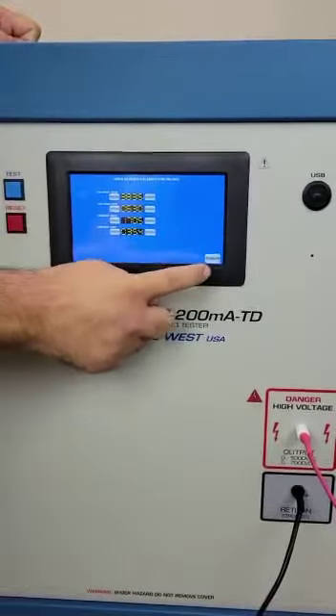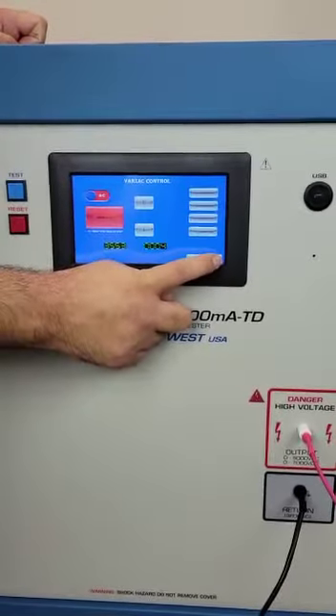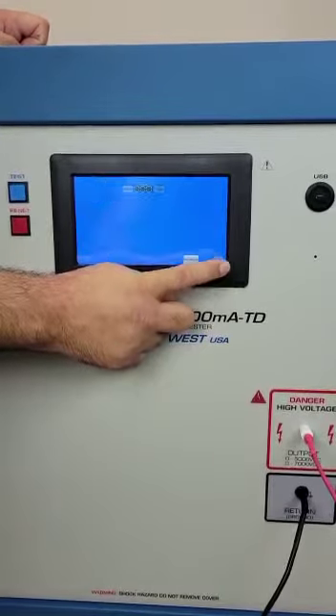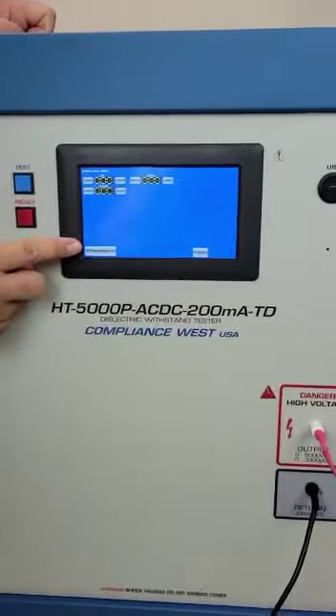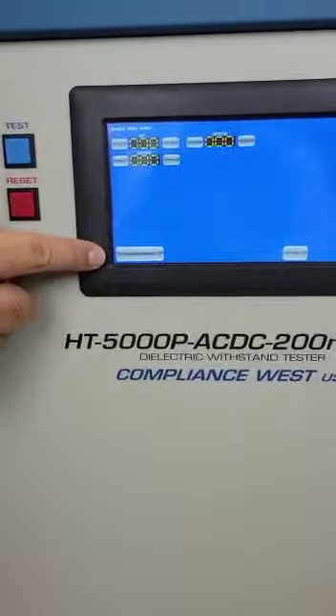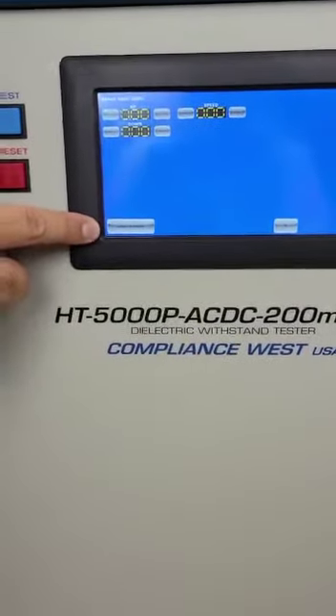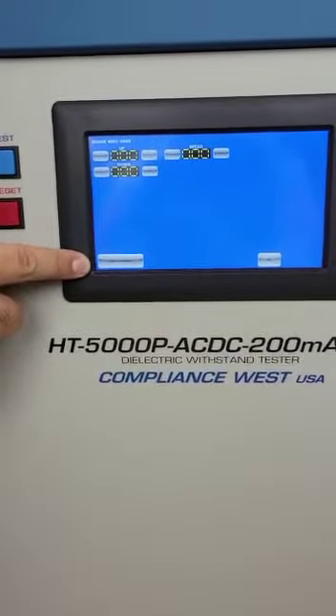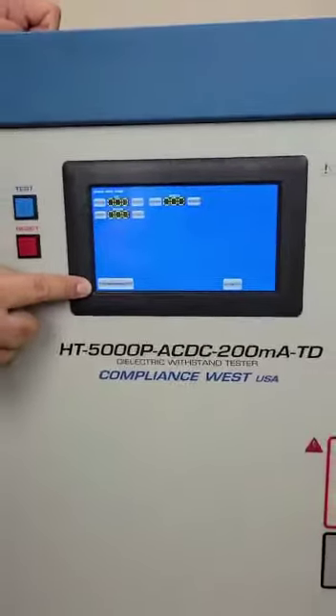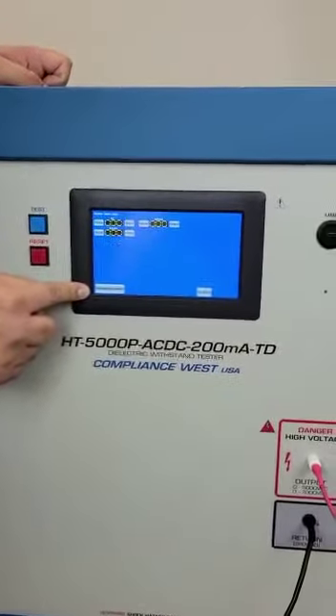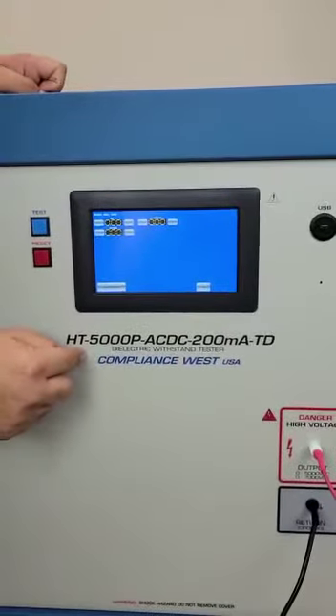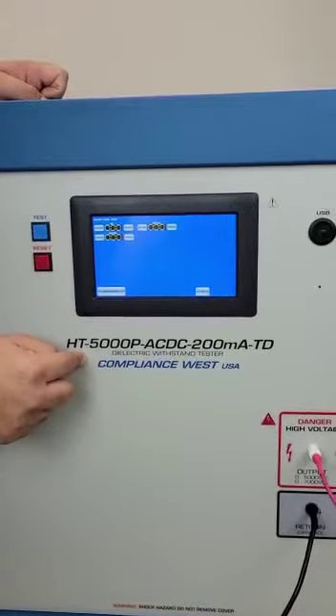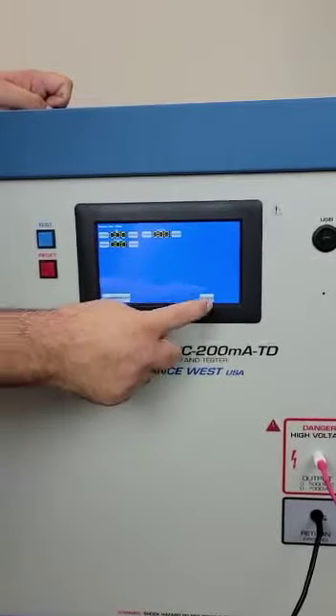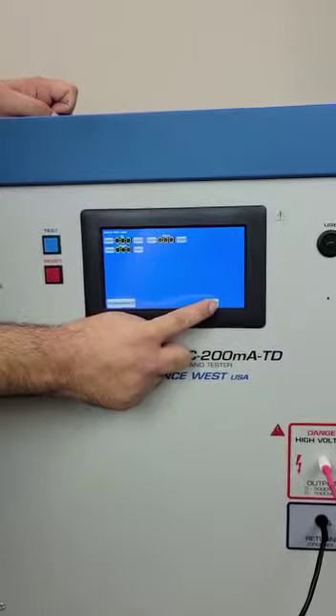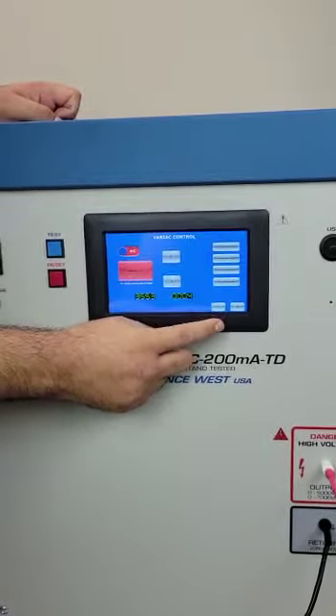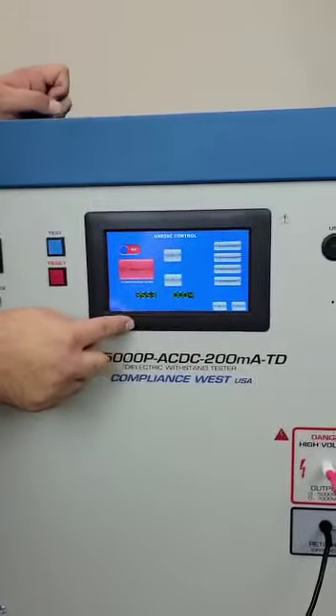Then you go next, next, next, and we have a button on the left bottom corner that says save to EEPROM. If you press that, the values that you enter on the calibration high and low point are going to be saved. We go back. Again, we're not pressing that because our tester is already calibrated.